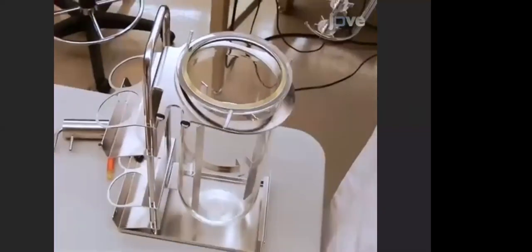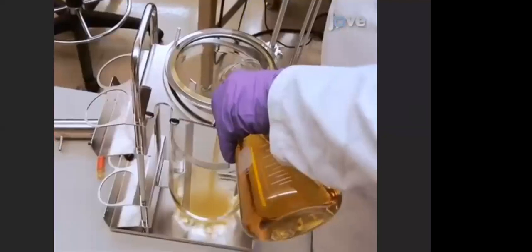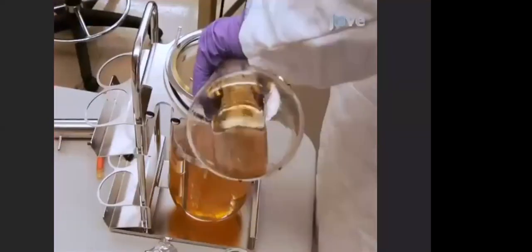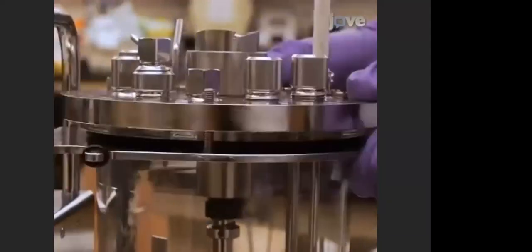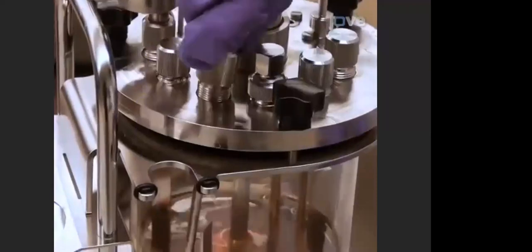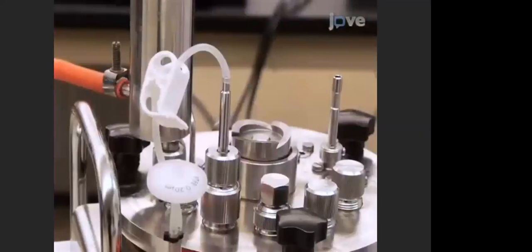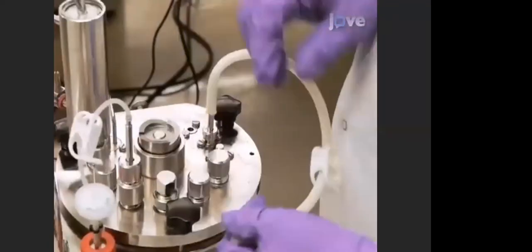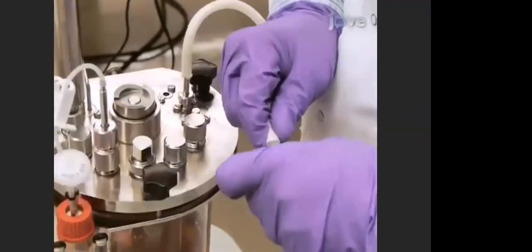To begin, add bacterial medium that is not heat labile to the clean vessel. Only add until maximum working volume is reached, which is 3.3 liters for a 5-liter total volume vessel. Mount the vessel headplate, ensuring that the O-ring seal is properly seated. Install the exhaust gas condenser. Install the harvest pipe into its 10mm port. Place a piece of tubing on top of it, connect to the sampling bottle, and clamp the tubing off. Install tubing and a 0.2 micron filter on the sparge inlet, and then clamp this off.